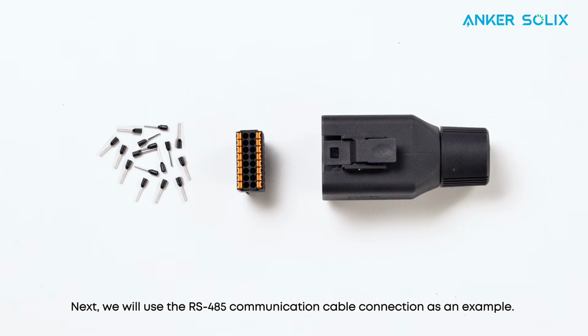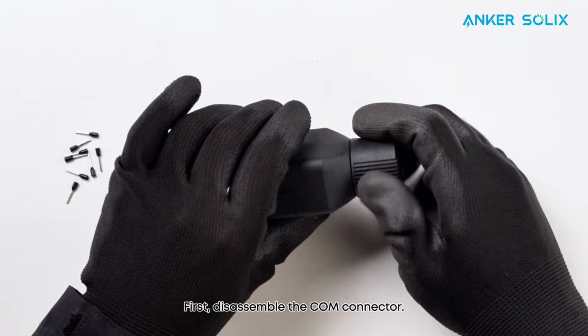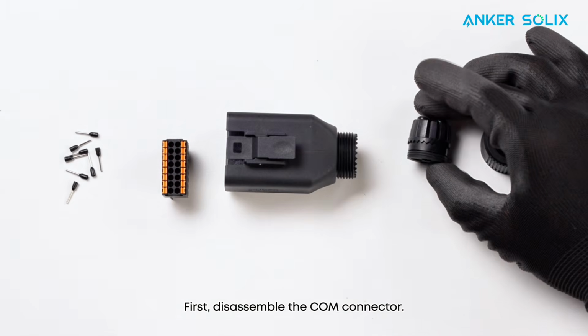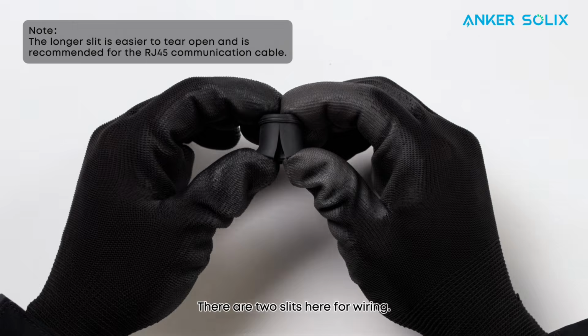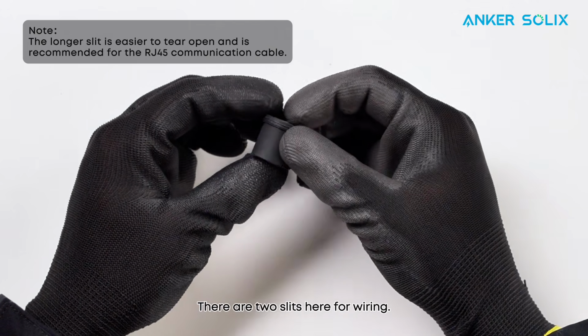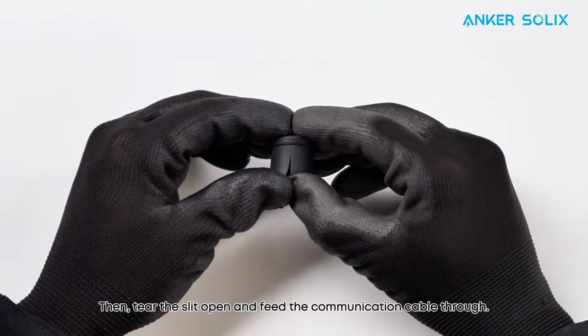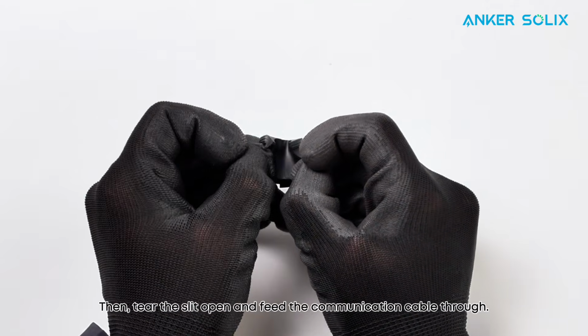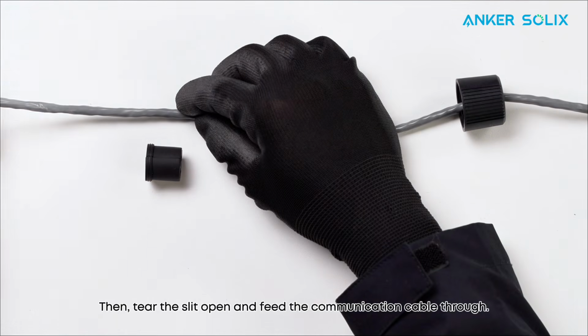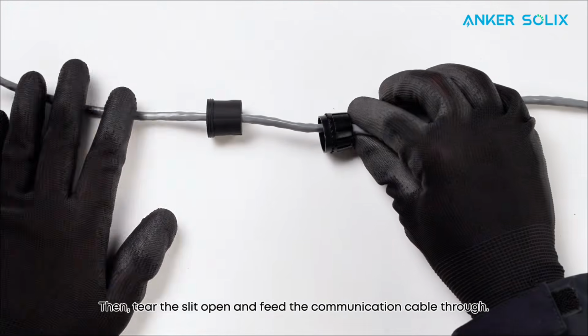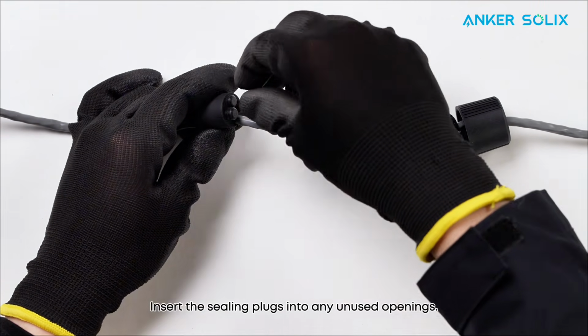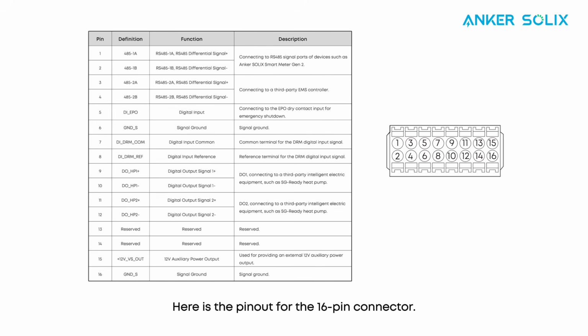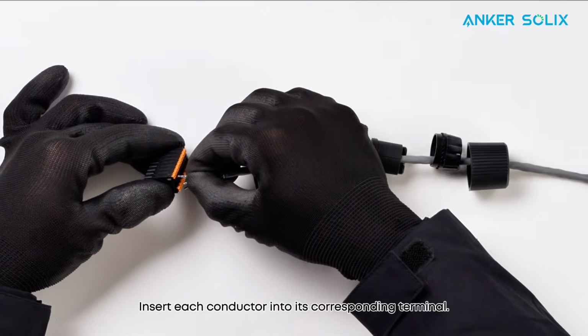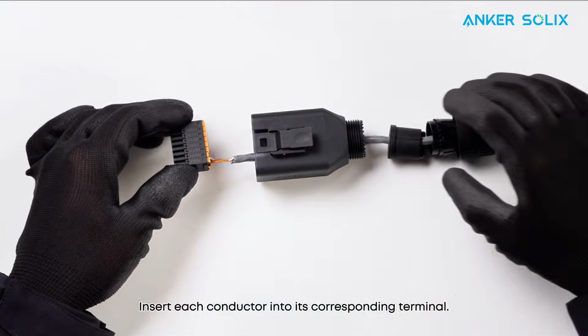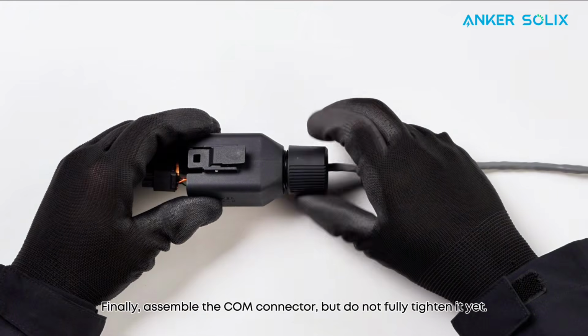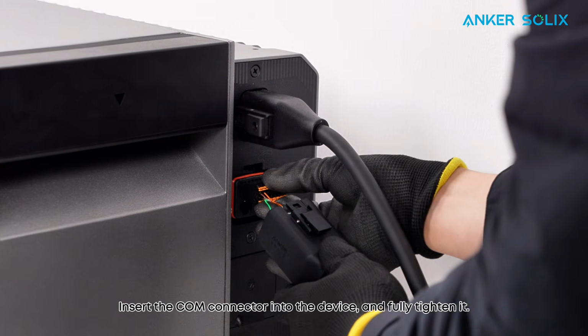Next, we will use the RS485 communication cable connection as an example. First, disassemble the COM connector. There are two slits here for wiring. Then, tear the slit open and feed the communication cable through. Insert the sealing plugs into any unused openings. Here is the pinout for the 16-pin connector. Insert each conductor into its corresponding terminal. Finally, assemble the COM connector, but do not fully tighten it yet. Insert the COM connector into the device and fully tighten it.